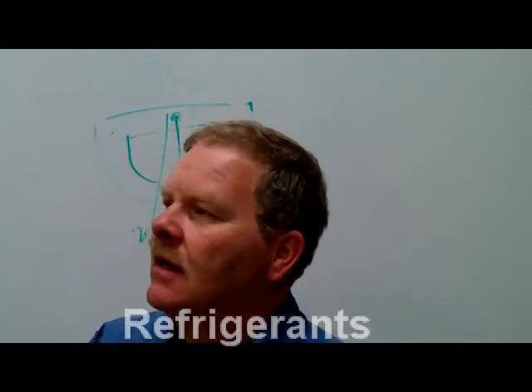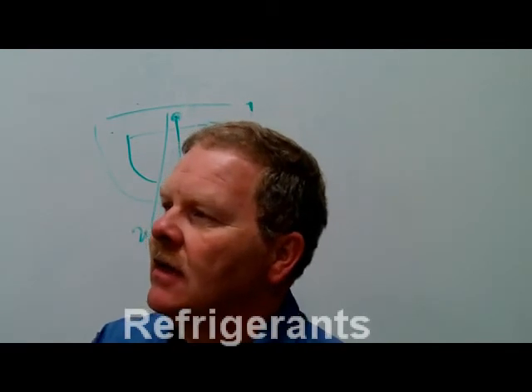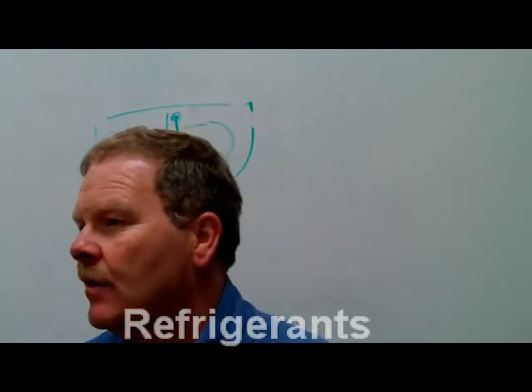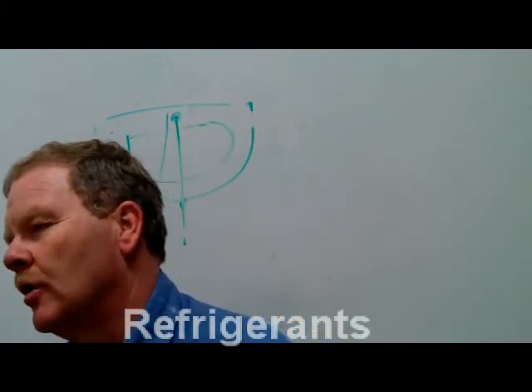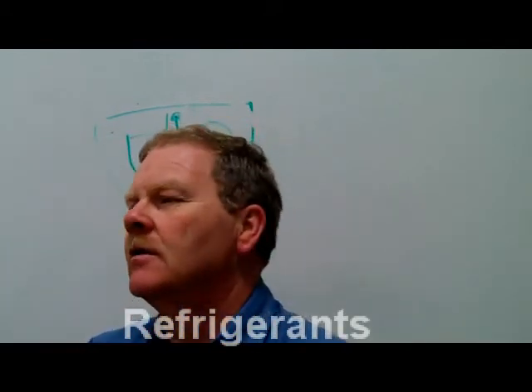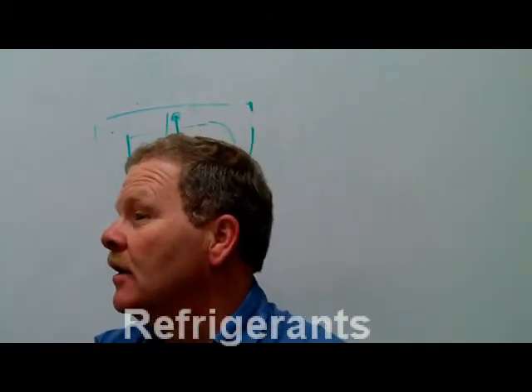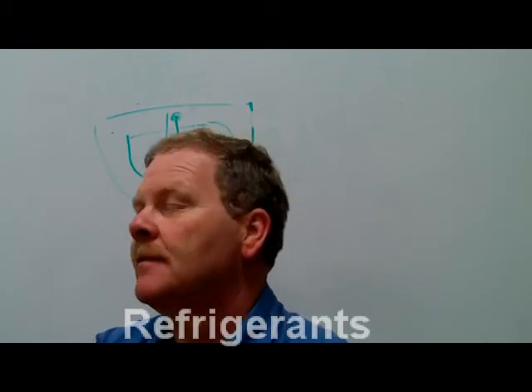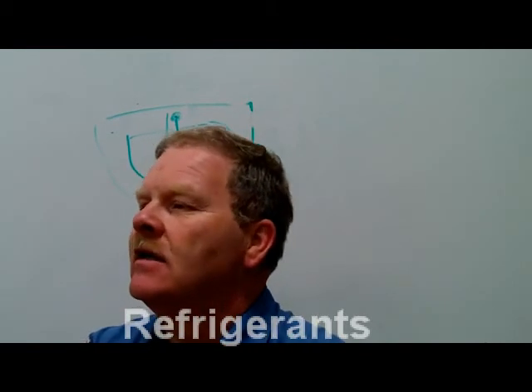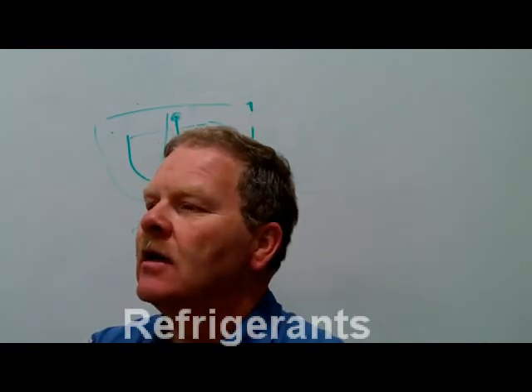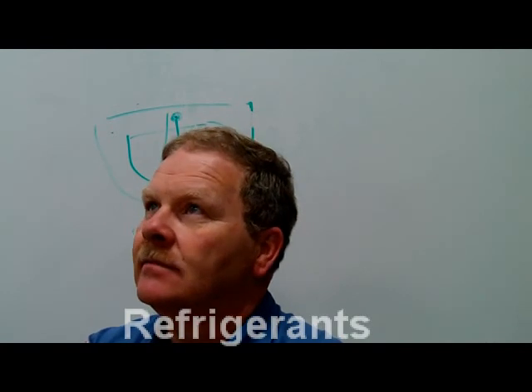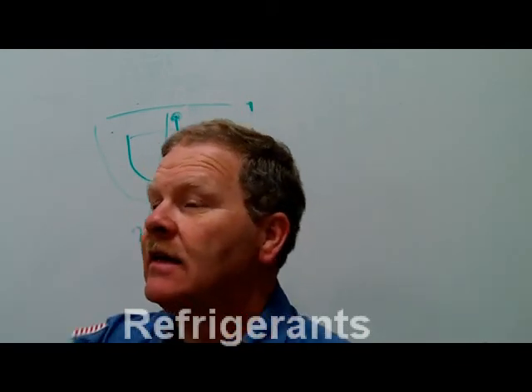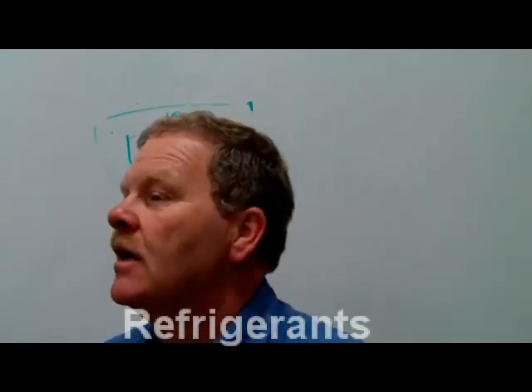It's real hot because of just the nature of what's going on in that refrigerant system. You're squeezing that refrigerant into a high-pressure gas. It goes through the condenser, and the condenser actually condenses into a liquid. And when it comes out of the condenser, it's a really hot liquid, unless you're operating a sub-cooler. Now, do you remember me telling you about a sub-cooler? Yes, I remember. It looks like a condenser. But basically what it does is after it has condensed the refrigerant back into a liquid, it cools it off.